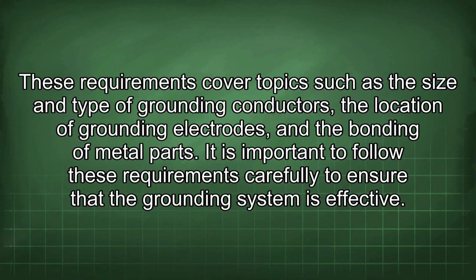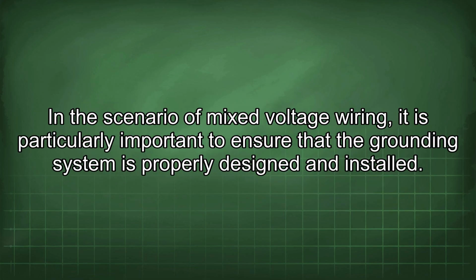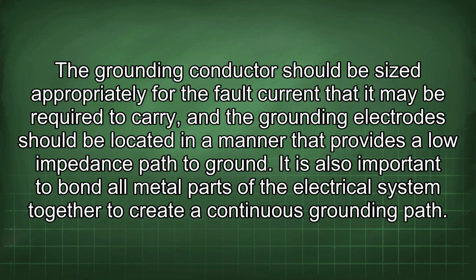These requirements cover topics such as the size and type of grounding conductors, the location of grounding electrodes, and the bonding of metal parts. It is important to follow these requirements carefully to ensure that the grounding system is effective. In the scenario of mixed voltage wiring, it is particularly important to ensure that the grounding system is properly designed and installed. The grounding conductor should be sized appropriately for the fault current that it may be required to carry, and the grounding electrode should be located in a manner that provides a low impedance path to ground. It is also important to bond all metal parts of the electrical system together to create a continuous grounding path.